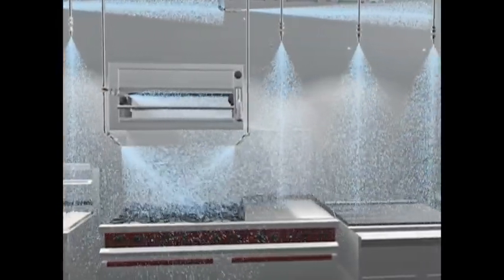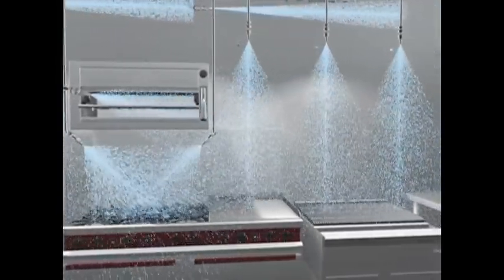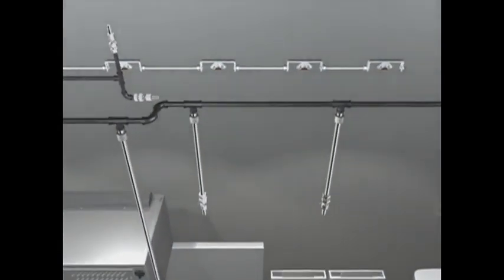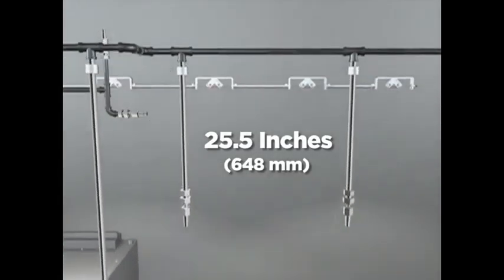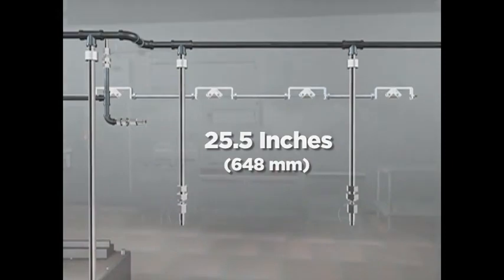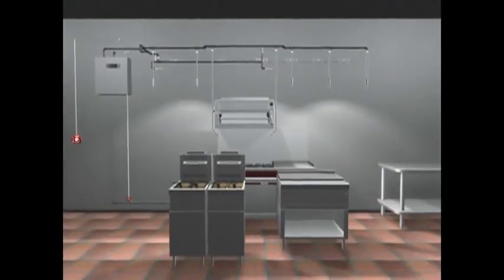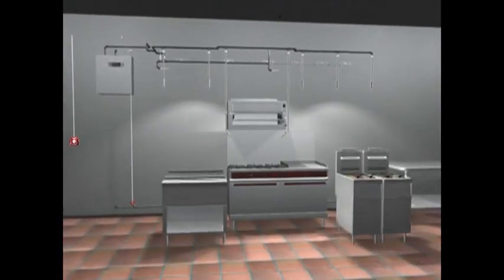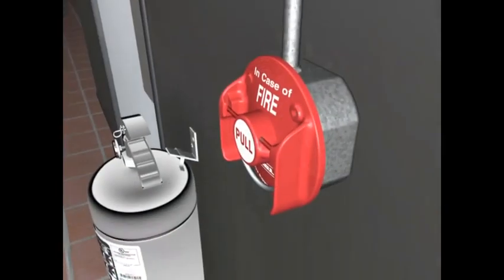And, like the R102, the Piranha system allows overlapping nozzle placement with as much as twenty-five and a half inches spacing. This permits you to replace or rearrange your appliances without interfering with your fire suppression scheme.